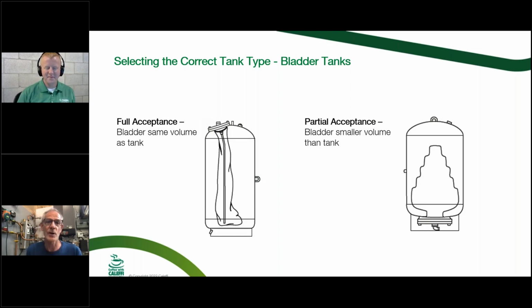And that comes up, Cody, I think with hydro separators all the time. Yeah, we've got non-ASME hydraulic and air and dirt separators and things like that that go up to 5 or 6 inches. And you could flip a coin some days as far as when they're getting used versus when they're not. A lot of it has to do with the AHJ in that particular area, and if they want an ASME tank or not, or for the Canadians, our friends north of the border, a CRN type tank.